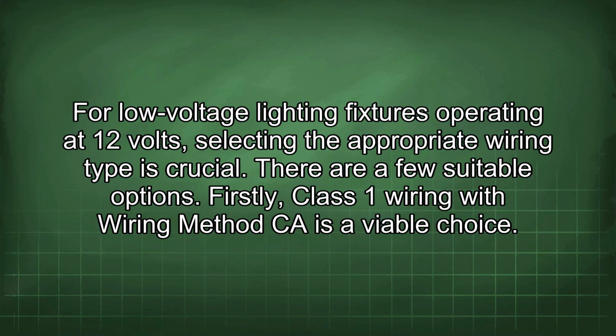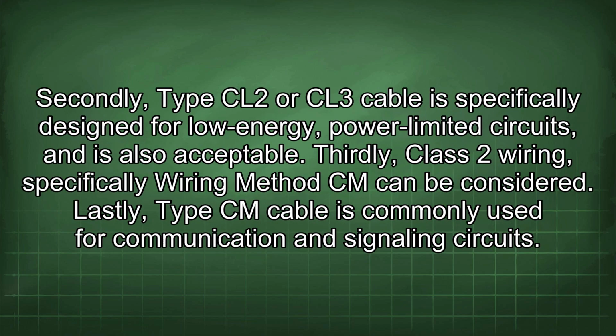For low voltage lighting fixtures operating at 12 volts, selecting the appropriate wiring type is crucial. There are a few suitable options. Firstly, Class 1 wiring with wiring method CA is a viable choice. Secondly, Type CL2 or CL3 cable is specifically designed for low-energy, power-limited circuits, and is also acceptable. Thirdly, Class 2 wiring, specifically wiring method CM, can be considered. Lastly, Type CM cable is commonly used for communication and signaling circuits.